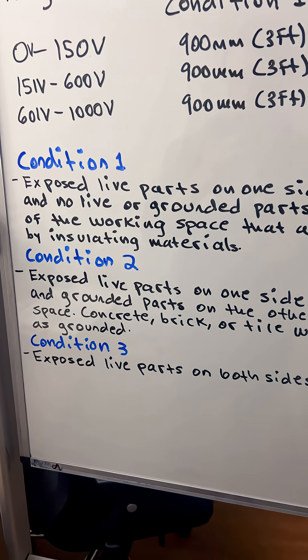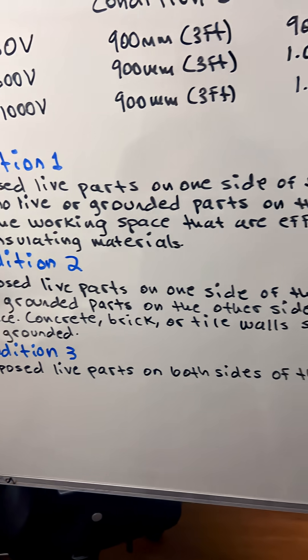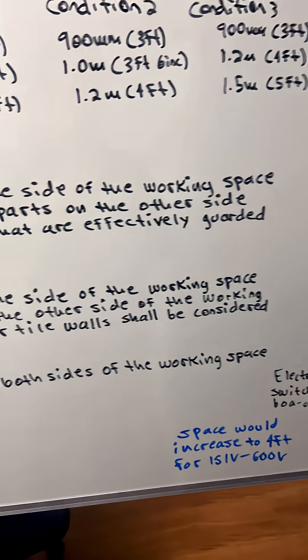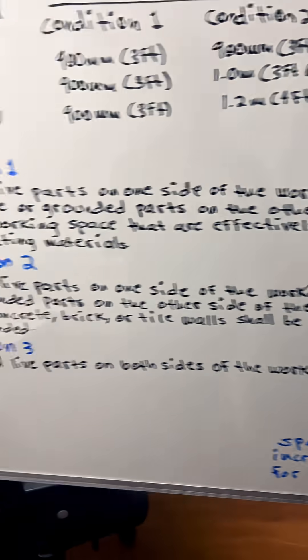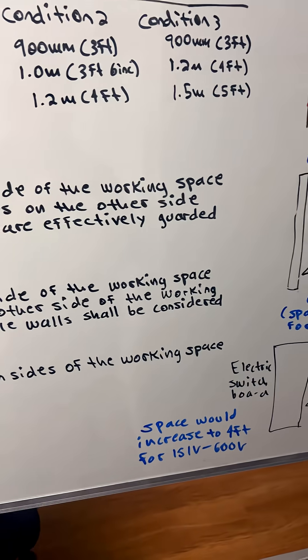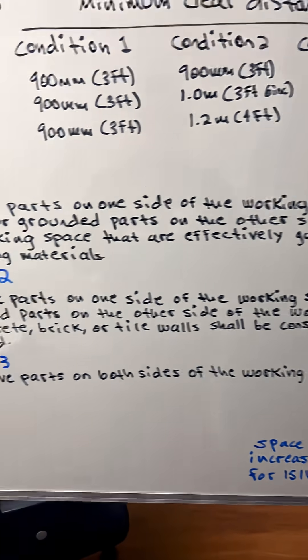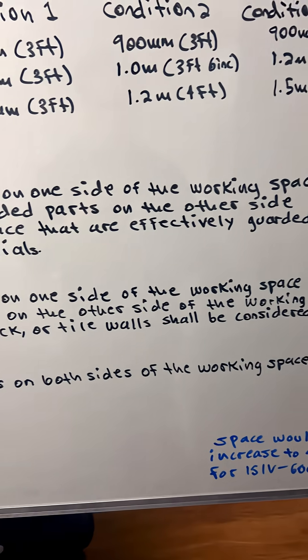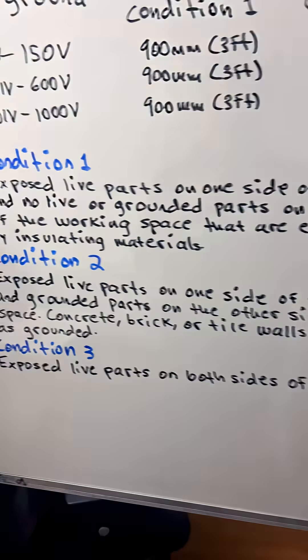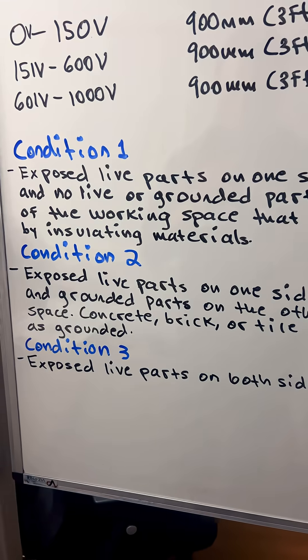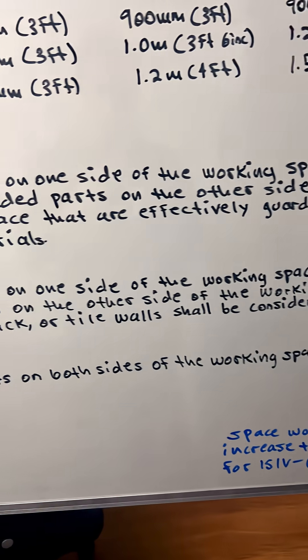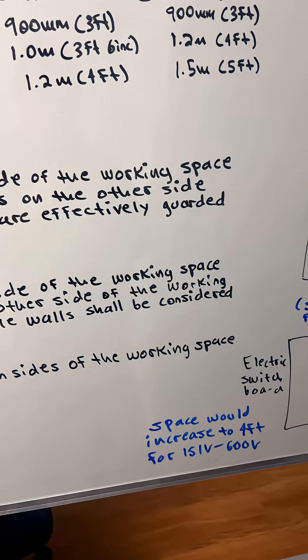For condition 2, it's exposed live parts on one side of the working space and grounded parts on the other side. Concrete, bricks, or tile walls should be considered as grounded. And for condition 3, it's exposed live parts on both sides of the working space.